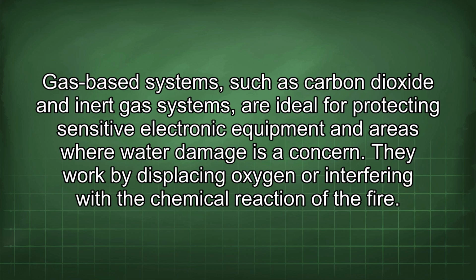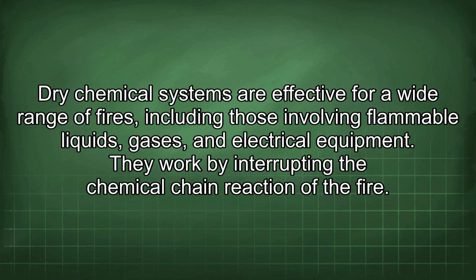Gas-based systems, such as carbon dioxide and inert gas systems, are ideal for protecting sensitive electronic equipment in areas where water damage is a concern. They work by displacing oxygen or interfering with the chemical reaction of the fire. Dry chemical systems are effective for a wide range of fires, including those involving flammable liquids, gases, and electrical equipment. They work by interrupting the chemical chain reaction of the fire.